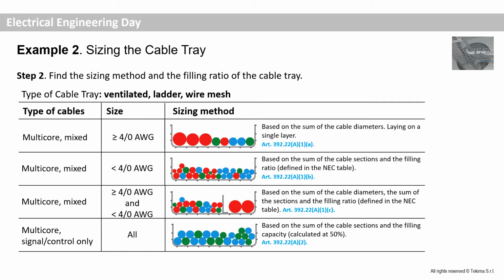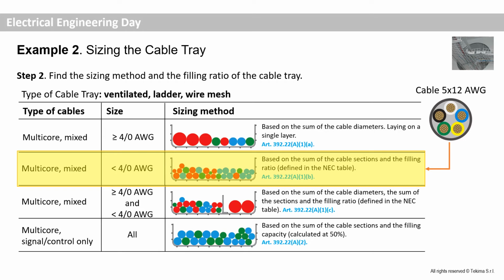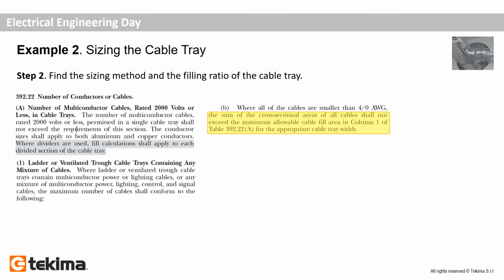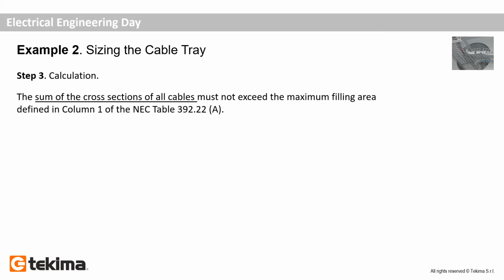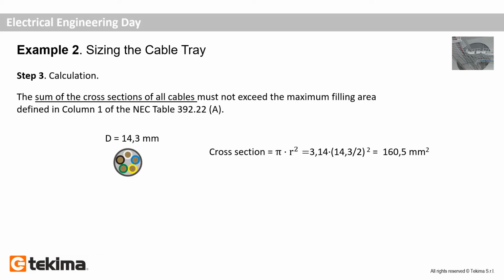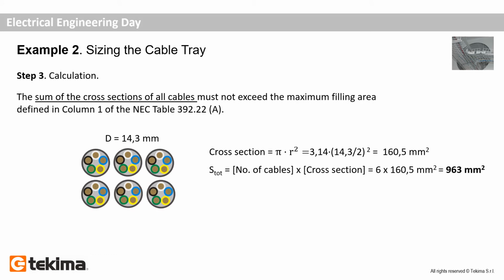For this example, we are considering a multi-core cable 12 AWG installed in a ventilated cable tray. That means we have to follow the rules defined in Article 392.22(A)(1)(b) that says the sum of the cross-sectional areas of all cables shall not exceed the maximum allowable cable fill area defined in the NEC. Step 3. Calculate the sum of the cross-sectional area of all cables. To do that, we have to calculate the cross-sectional area of a single cable and then multiply by the 6 cables contained. So as for example 1, we have 963 square millimeter.